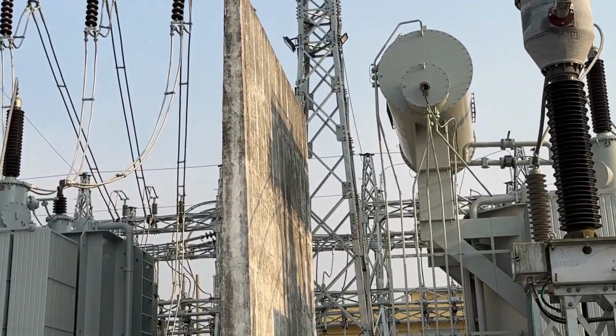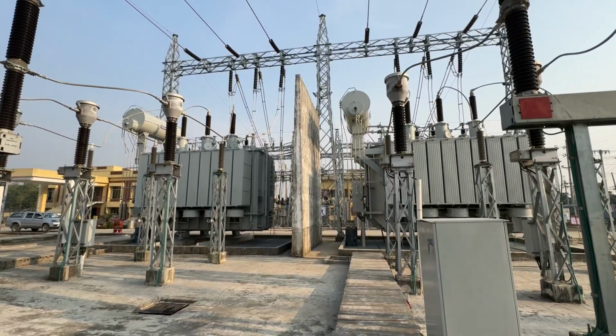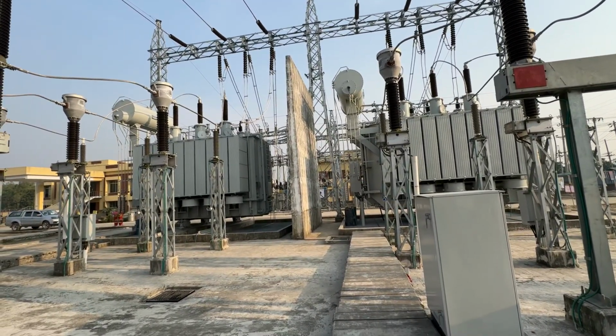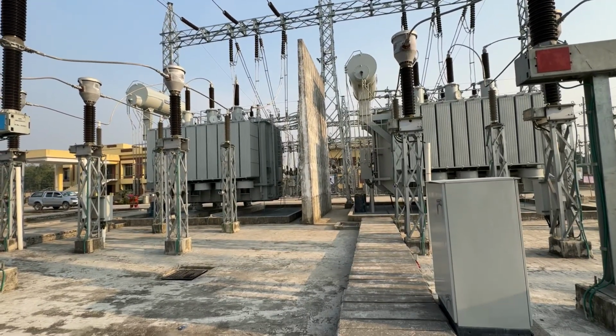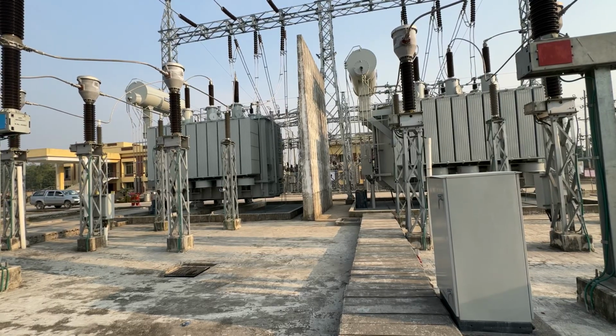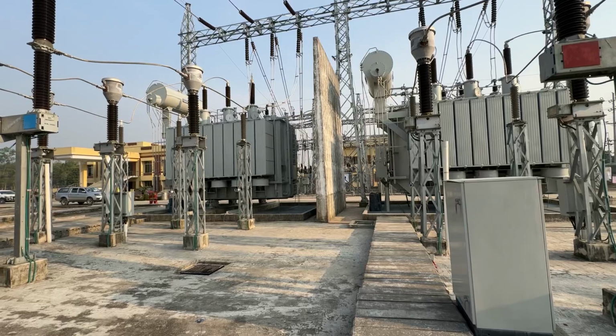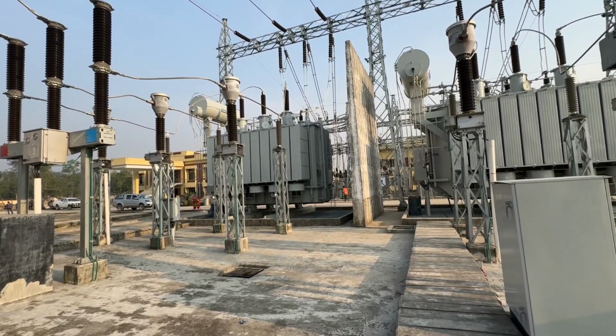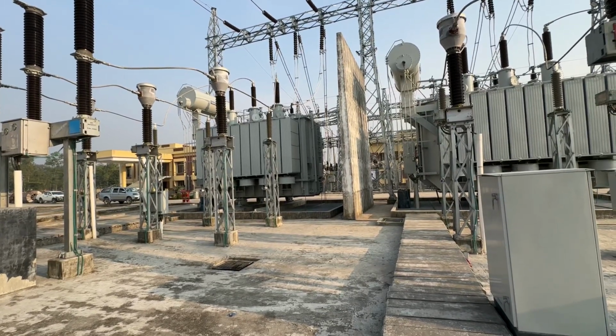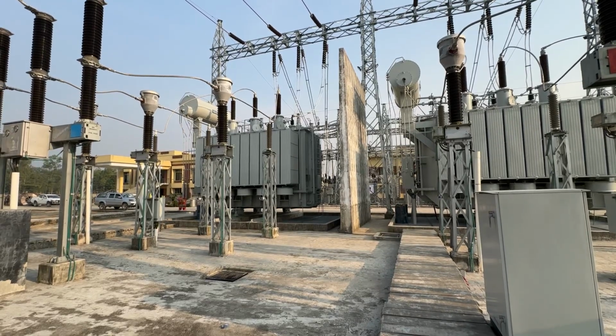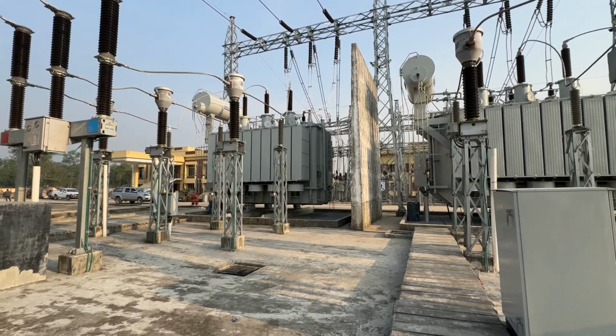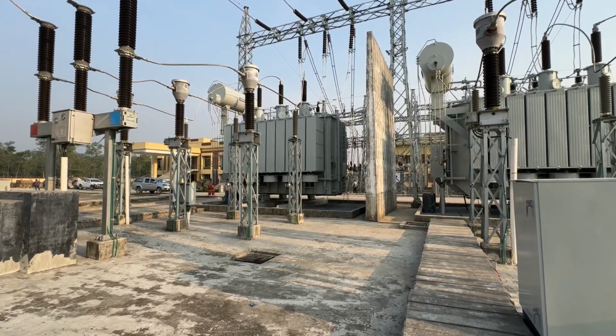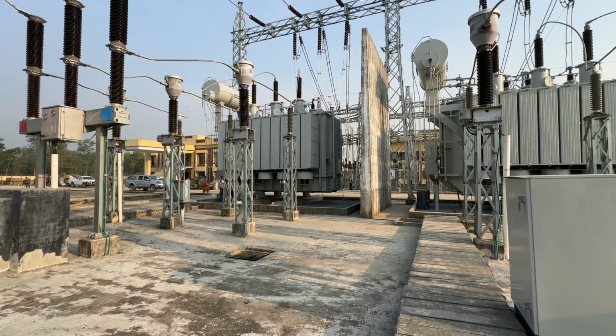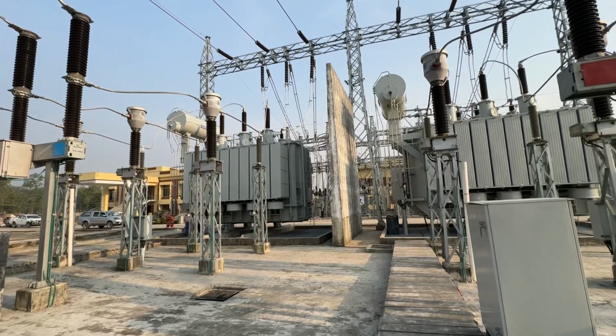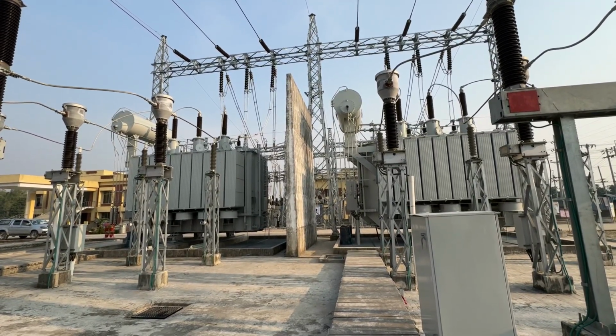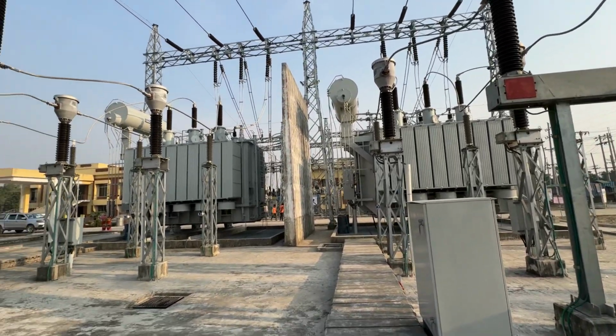This is the firewall. It is recommended to place it between any two transformers, because in any circumstances, if there is a hazard or any electrical accident, a fire may catch on the transformer. If any fire happens to a transformer and the transformer comes out, it is very dangerous, and in a very rapid time the fire can catch other equipment. The purpose of this guide wall is to prevent the second transformer from the fire.